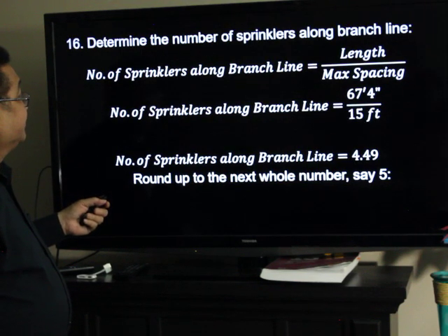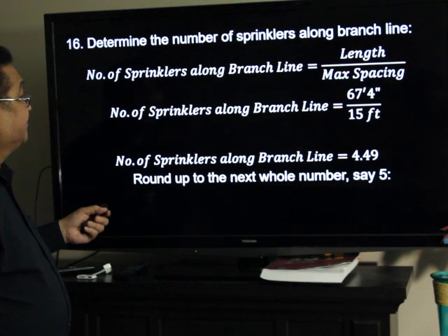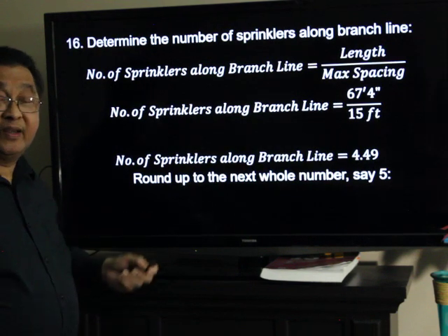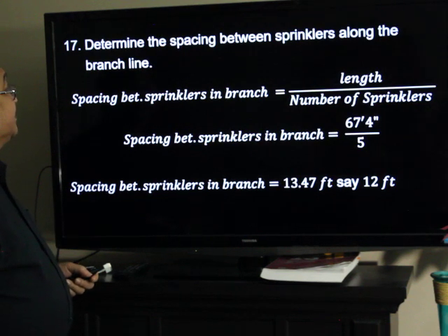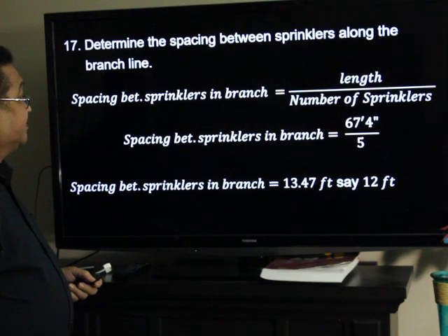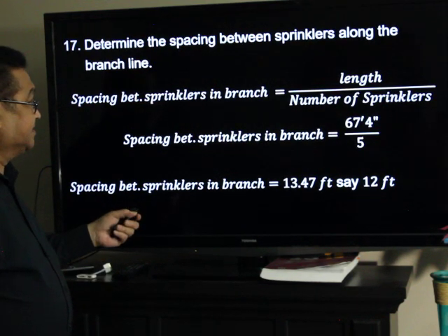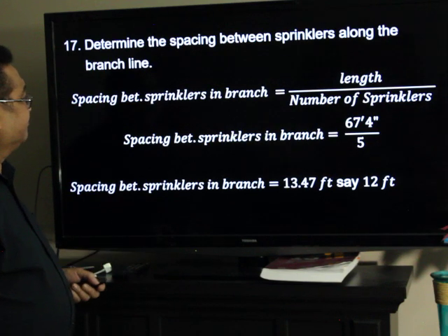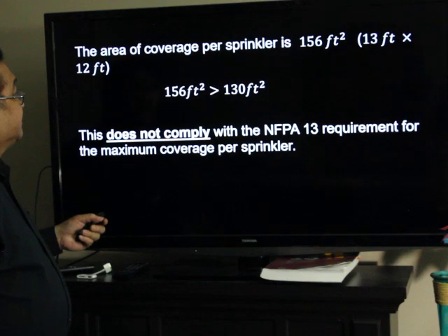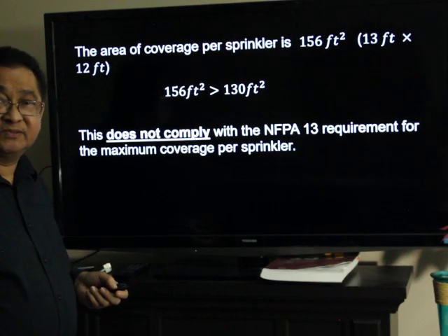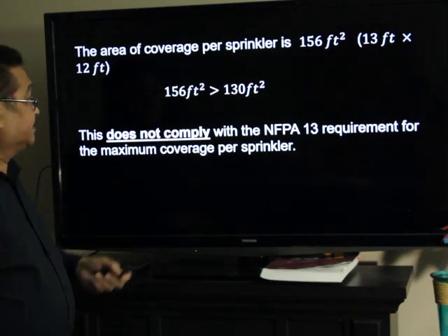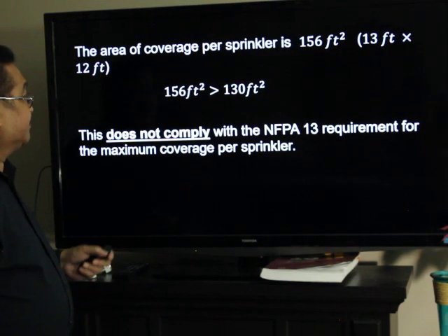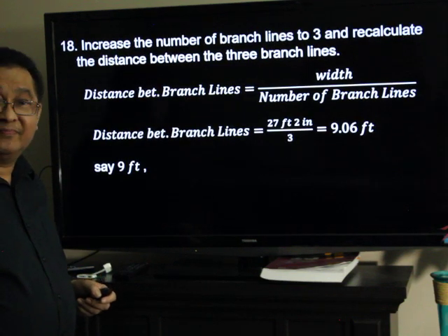Determine the number of sprinklers along the branch line: the length divided by maximum spacing — 67 feet and 4 inches divided by 15 — we have 4.49, and we round up to 5. Determine the spacing between the sprinklers along the branch line: 67 feet 4 inches divided by 5, the result will be 13.47 feet — just to be safe, say 12 feet. The area coverage per sprinkler is 13 feet by 12 feet, which results in 156 square feet. Since it is greater than 130 square feet, it doesn't comply with the NFPA 13 requirement. Therefore, we will increase the number of branch lines to 3.